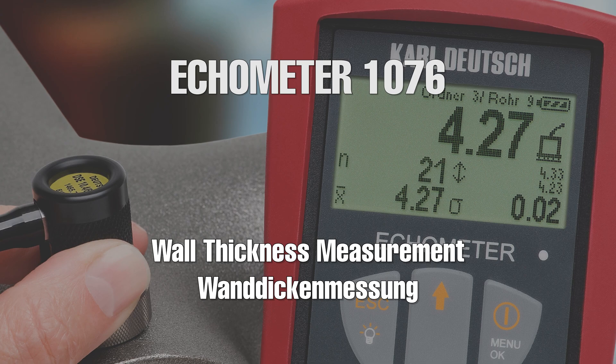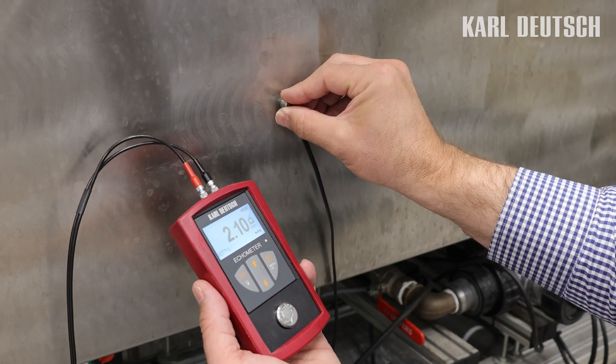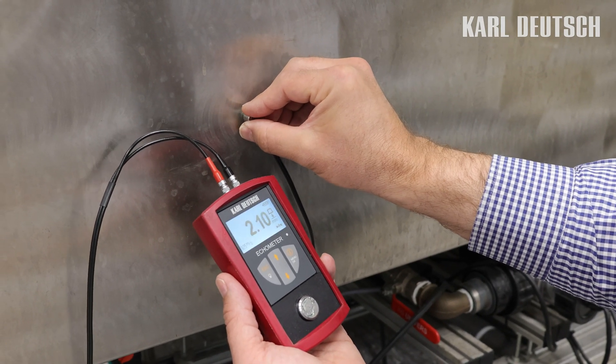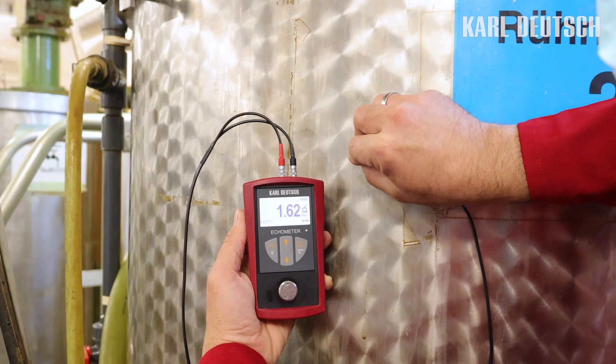Welcome to Karl Deutsch. The ECHOMETER 1076 is a measuring device for determining wall thickness. It is used whenever a mechanical measurement with a caliper gauge is not possible because only one side of the wall is accessible, such as on pipes and vessels.